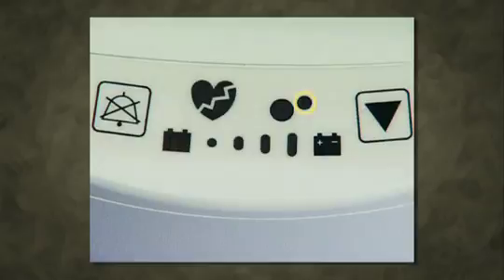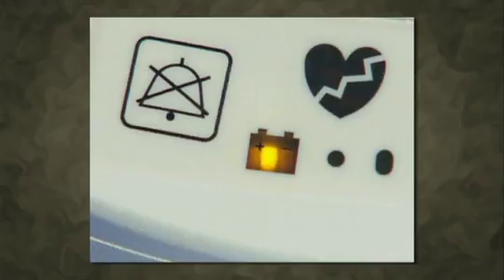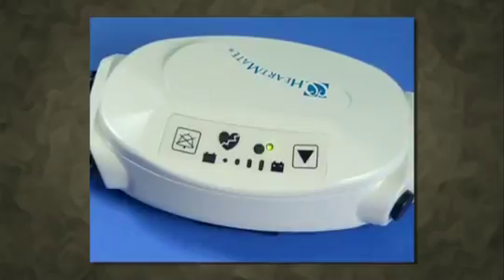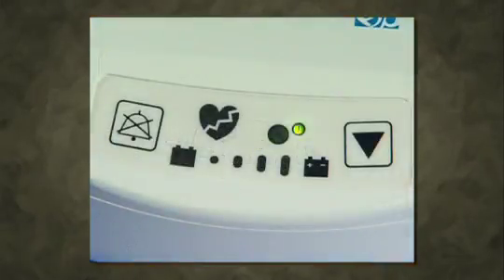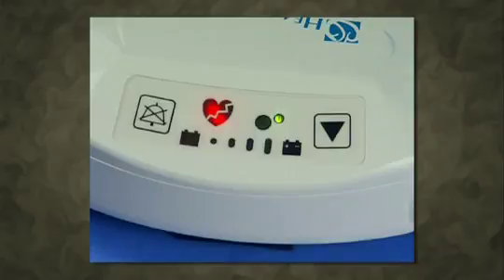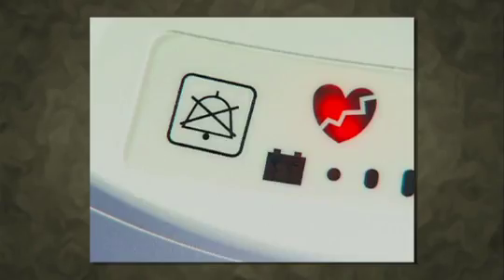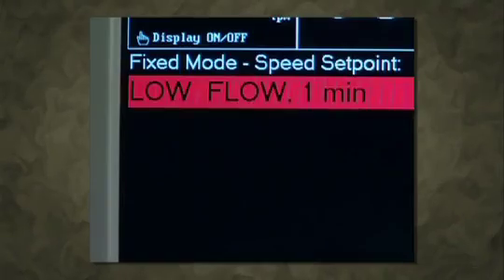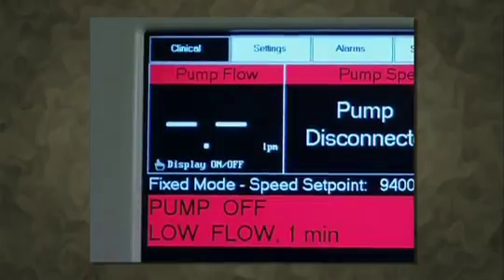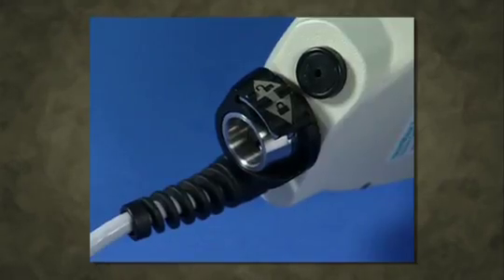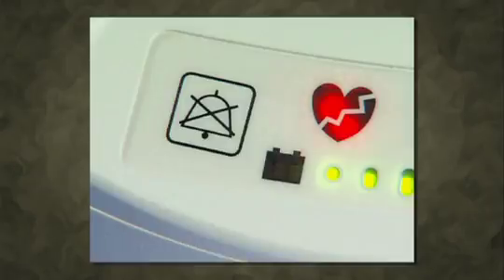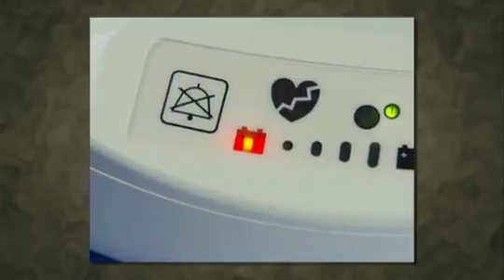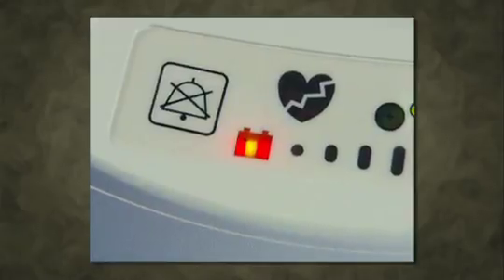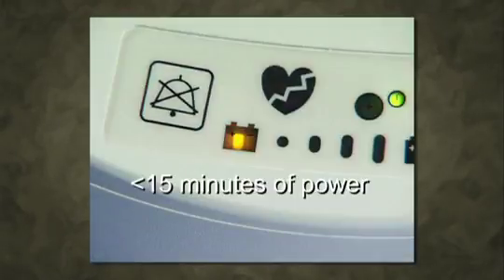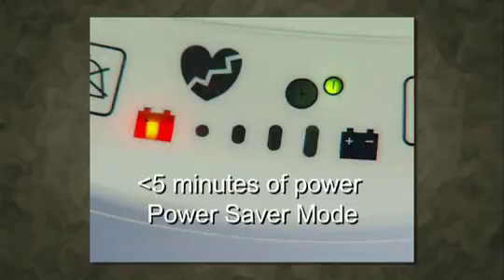Now, while you're not required to interpret all of the lights and alarms, you can know a few. If the pump is receiving power, you will see a green circular light illuminated solidly. If you see a red broken heart illuminated, which would be accompanied by a steady audio tone, the patient is in a life-threatening situation. A red heart alarm goes off when the pump flow is dangerously slow or is stopped, the system controller, and therefore the power supply, has become disconnected from the pump, or if the pump is not working properly. Seeing the battery symbols light up means the system power is running out. A yellow battery indicates 15 minutes of power is left, while a red battery means only 5.